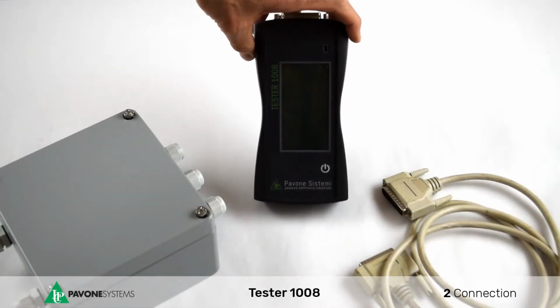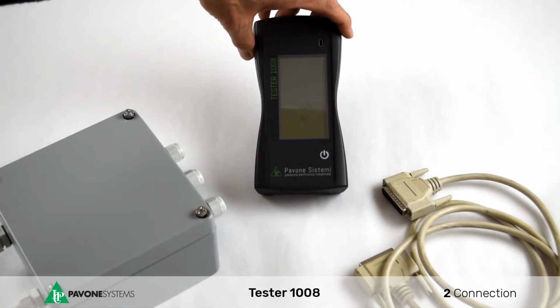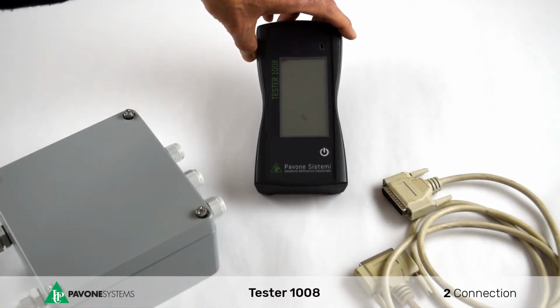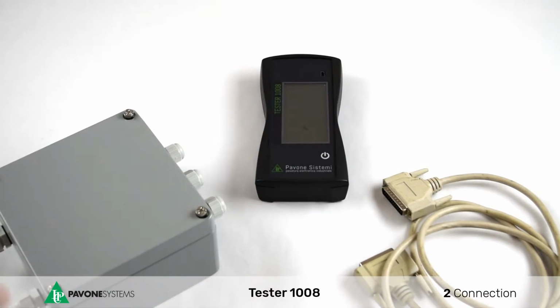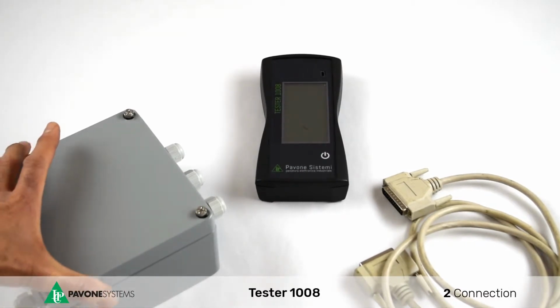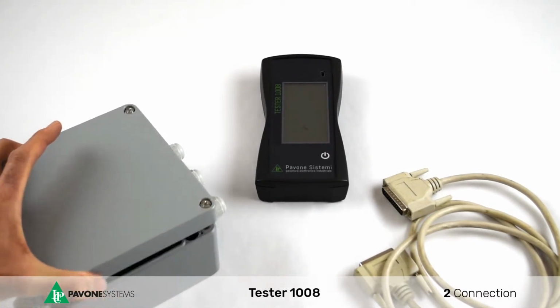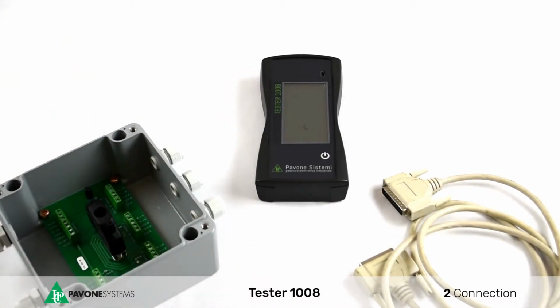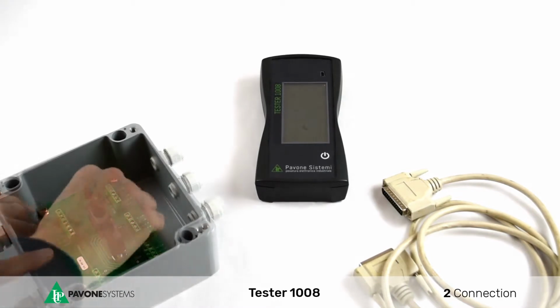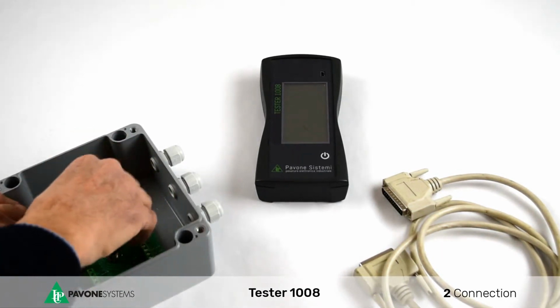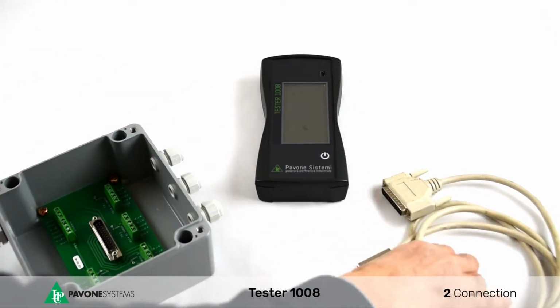In order to use Tester 1008 correctly, you have to connect the instrument to the junction box by using the white cable. Open the junction box CGS4 and remove the central plug from the card. Take the white cable and connect it to the junction box.